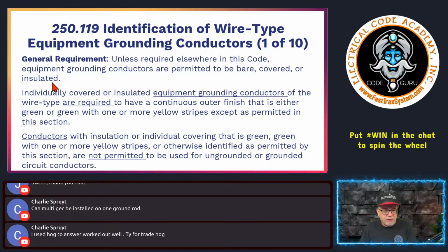So you've got your general rules in 250.119, and then you have the statement of unless required elsewhere. The NEC says you meet the requirements of chapters 1 through 4, and obviously Article 250 is in chapter 2, but you meet those rules generally throughout the NEC, unless they're modified or supplemented somewhere else in the NEC in chapters 1 through 7. So chapter 6, which is pools, is going to modify or supplement something under the general requirement in chapter 2. So that's kind of how that works. When you see something in the code that says unless required elsewhere, then you follow the general rule. But somewhere else in the NEC may say, wait a minute, I need you to do this, and that wouldn't be the normal, but we need you to do it a little different. Then that's what you do. You follow the code that way.